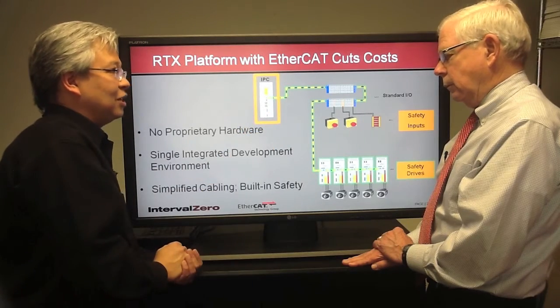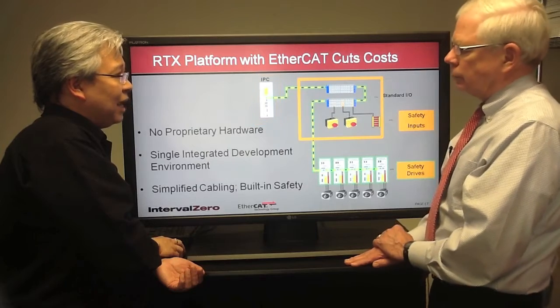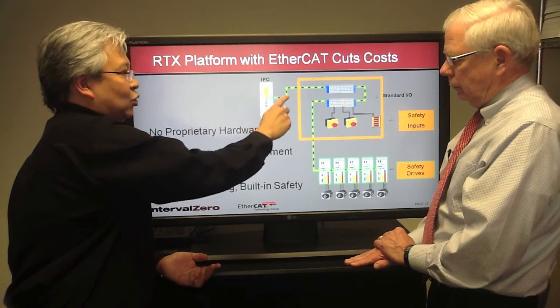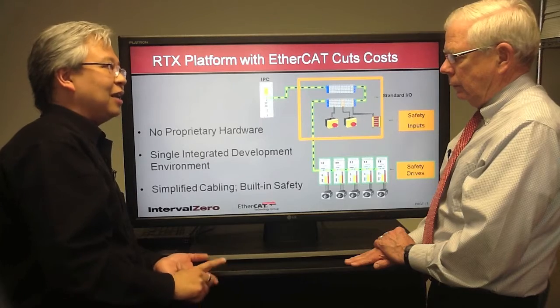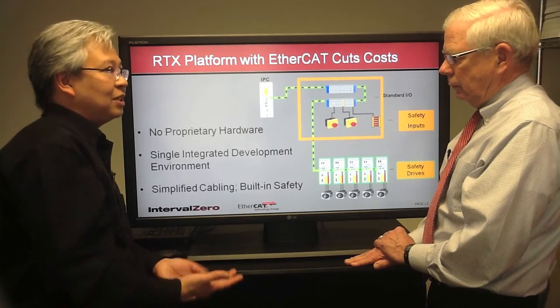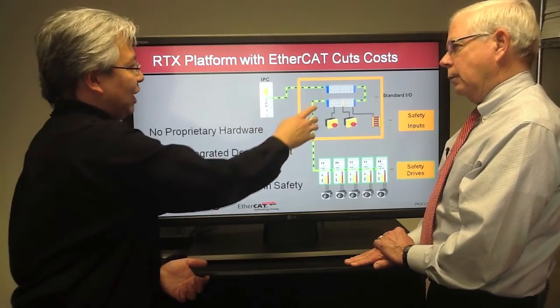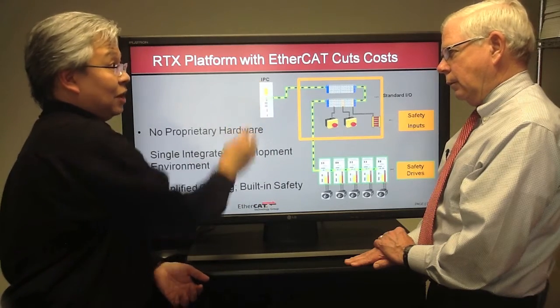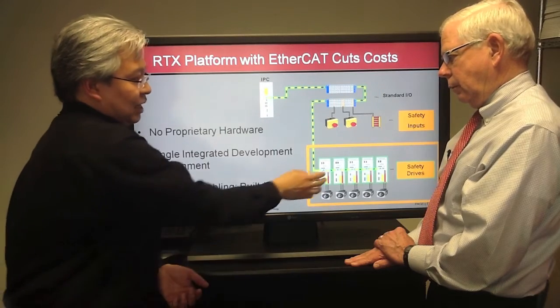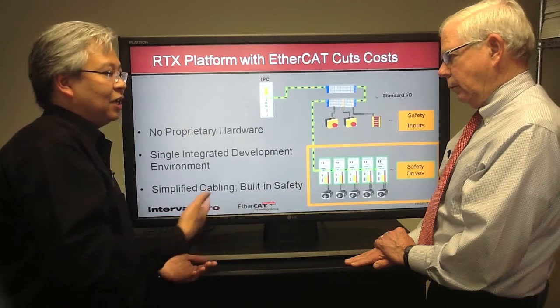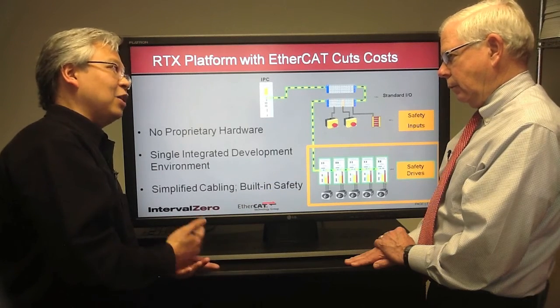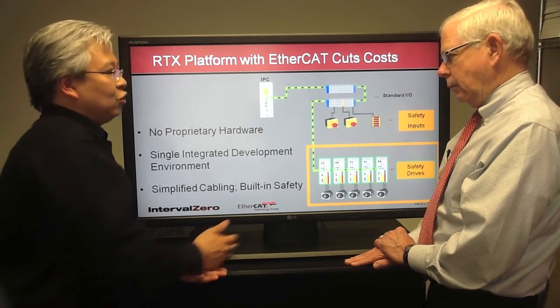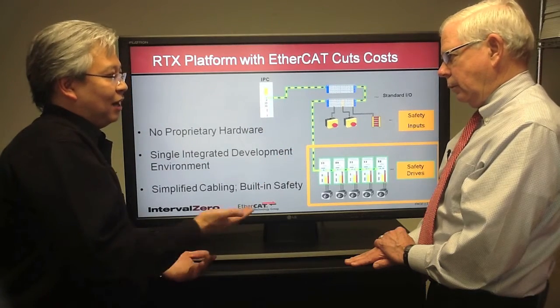A lot has transformed just in the industrial PC itself. Coming out to the cabling, the change is pretty drastic. What's really effective today is that you have an integrated bus for both communication and safety — EtherCAT delivers that. You're no longer required to have a separate safety bus and separate safety logic. It's all integrated into one CAT5 cable, and your safety logic itself is built into the industrial PC as part of your application. Going further down, it's integrated into the drives — EtherCAT safety drives that have the hard logic inside, looking for safety messages coming across the bus from your controller. Truly drastic savings and streamlining of your wiring.